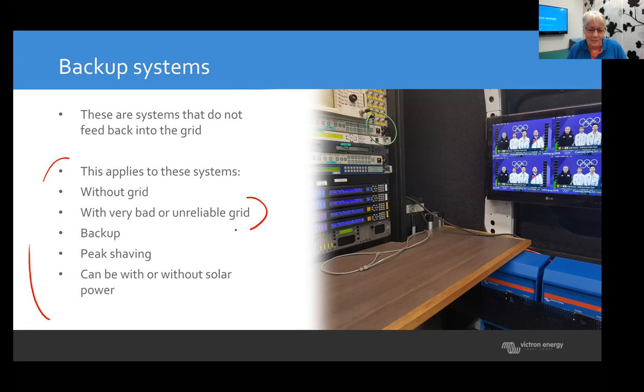So that's when backup comes into play. Peak shaving - every now and then you turn on a really big load, but your AC is only a certain amount. You just temporarily top it up with an inverter until the big load is off, and then you get battery charging again. So you're using the power assist feature of the unit.